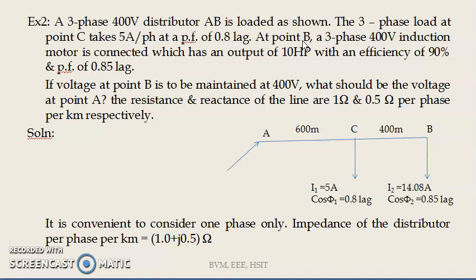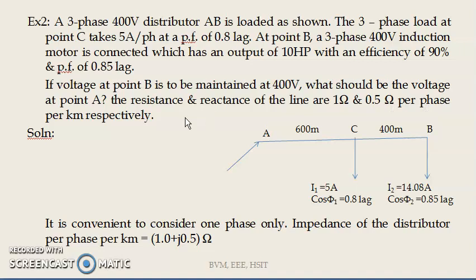At point B, a three phase 400 volt induction motor is connected which has an output of 10 HP with an efficiency of 90% and power factor of 0.85 lagging. If the voltage at point B is to be maintained at 400 volts, what should be the voltage at point A? The resistance and reactance of the line are 1 ohm and 0.5 ohm per phase per kilometer respectively.